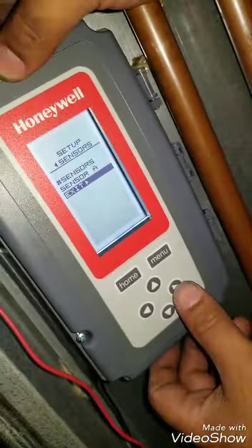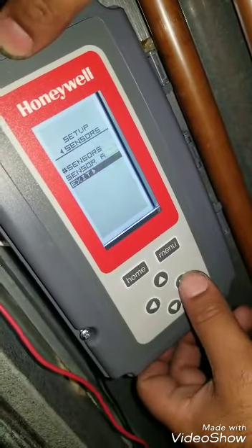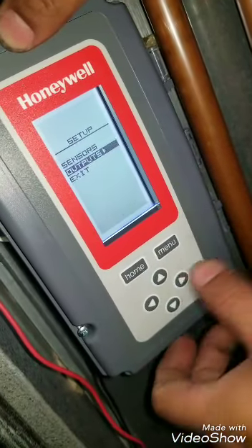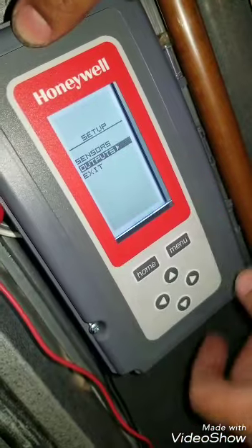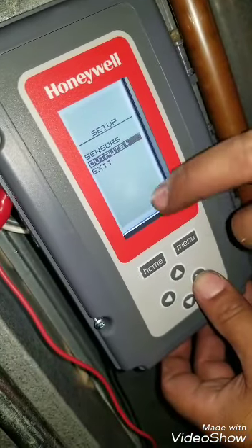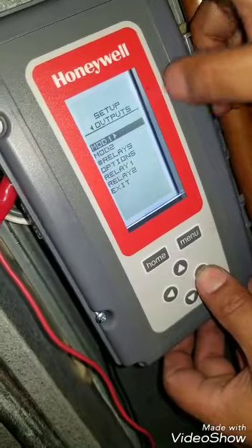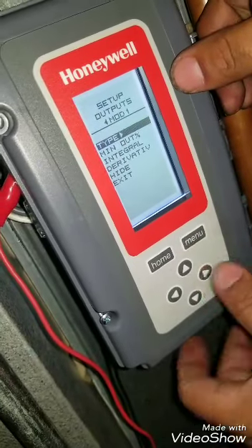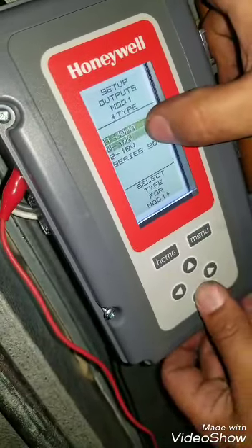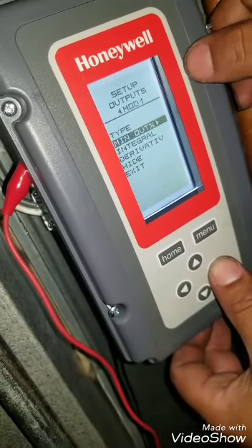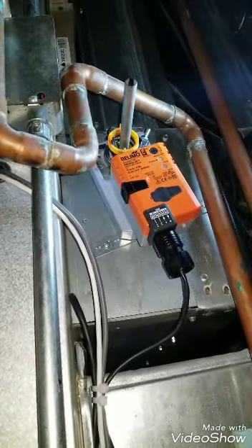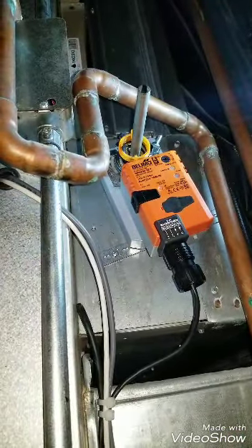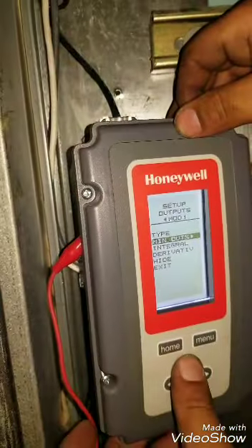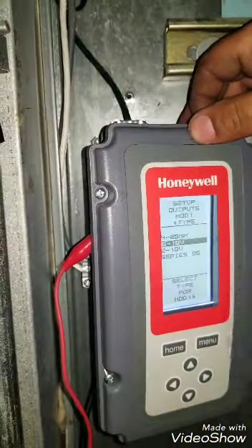So from there, you did your sensors. You can go back to exit. Now your output. After sensors, you got to set up your outputs, which is from this to the Belimo. So you go to mod 1 and you go type. The type is also 0 to 10. Enter. And you're going to see your damper just closed. It was open a little while ago. You're going to see it close. Okay. So basically, output from here to the Belimo is 0 to 10.